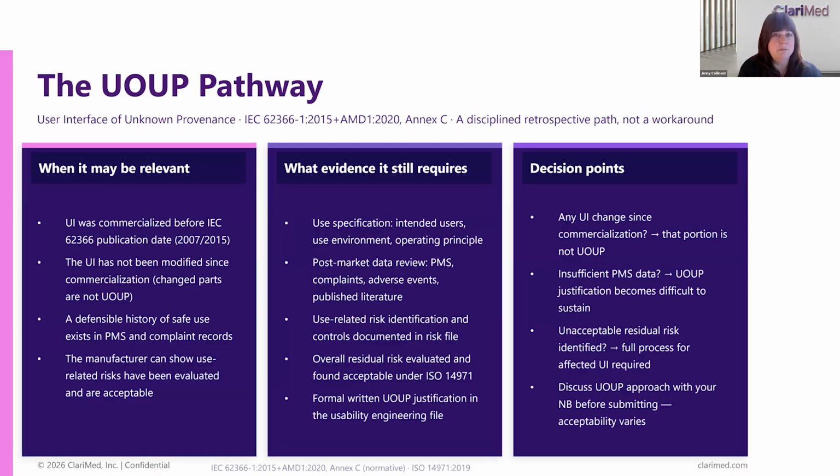And it's not for all scenarios. There are a couple of really major things that you need to be able to meet the conditions of before you can even progress this route. Your user interface needs to have been on the EU market before February 2015. Although I've actually recently seen challenge that it should have been before 2007, which is the first date of the issuance of 62366.